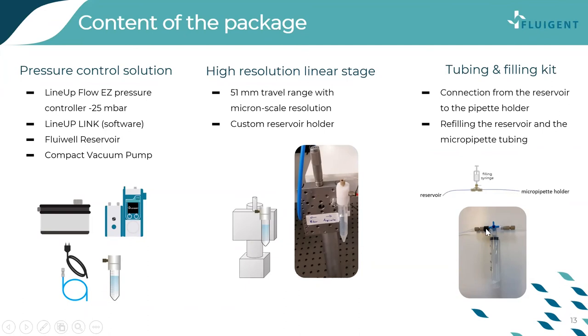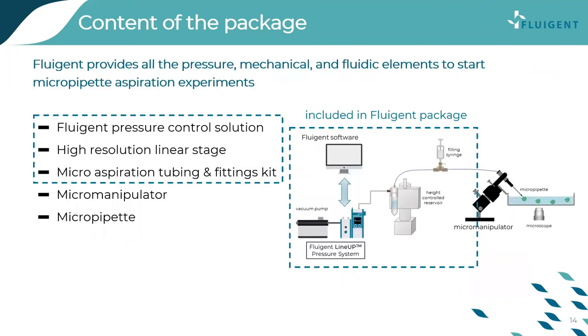There is a two-way valve that allows injection either into the reservoir part or the micropipette holder part. Thanks to this, you don't need to remove the reservoir and refill it — instead, simply use the tubing and filling kit to refill the reservoir and then switch the valve. In summary, the package includes the pressure control solution, the linear stage, and the microaspiration tubing and filling kit.